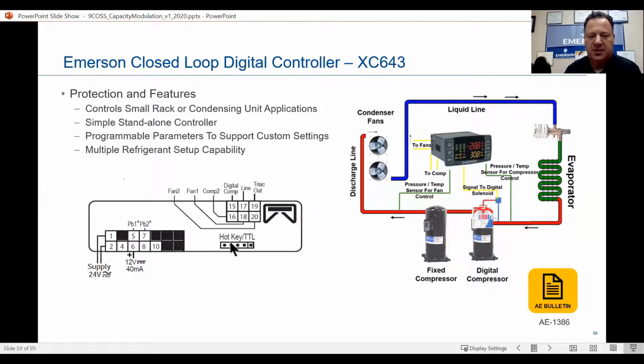So that's pretty cool. Got a hotkey here, which basically means that it's like a thumb drive. You're pushing it in there. A lot of times, if they have multiple coolers or freezers or whatever, they'll take their hotkey and program one, and then they'll take the hotkey out and just move it on down the line and program the rest of them the way it is. That's done very commonly with the superheat controllers and what have you out there, okay?